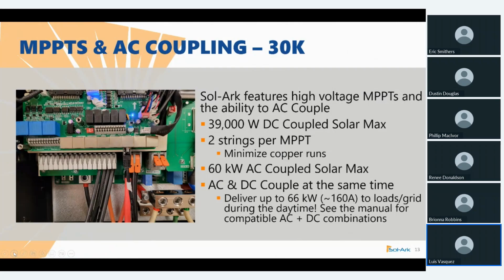You can connect up to 2 strings per MPPT, and if you want to AC couple - say you have an existing system and want to AC couple it to the Sol-Ark - you can easily do it, and we can go as high as 60 kilowatts connected to the Sol-Ark in AC coupling mode.